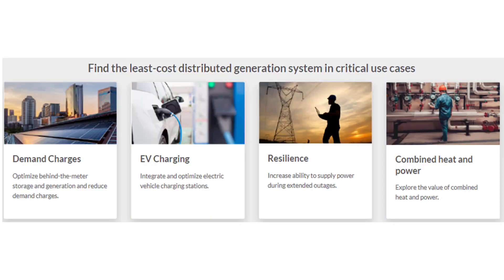Homer Grid's main value proposition is reducing utility charges by using solar and storage to shift and smooth peak utility usage to times when rates are lower. Demand charges are based on the maximum load, typically for just 15 minutes. Time-of-use rates provide less expensive electricity at certain times. Solar and storage together can reduce both these rates.